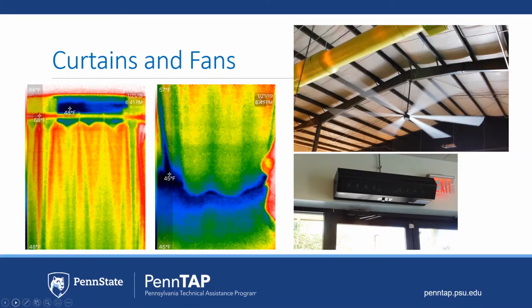You may notice this when you walk into a food store, you get that gust of air that greets you when you walk into the place. The Pacific Northwest National Laboratory has calculated the average energy savings from an air curtain for a commercial building to be about 4%. To take advantage of these savings, you need to use the air curtain during the wintertime, the summertime, and on windy days.